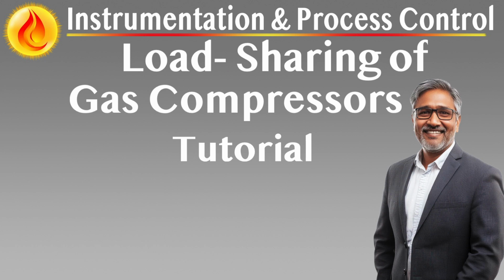Load balancing equalizes surge proximity and performance distribution in parallel compressor operation. Overview. Load balancing is the critical function within a parallel compressor control strategy that ensures all machines operate at an equal margin from surge. Rather than focusing on equal speed or flow, approaches which often fail due to internal performance differences, load balancing uses real-time surge deviation data to equalize risk and workload across the compressor train. By dynamically adjusting each compressor's output based on how close it is to its surge limit, the system prevents premature recycling of any single unit, enhances mechanical reliability, and optimizes process efficiency.